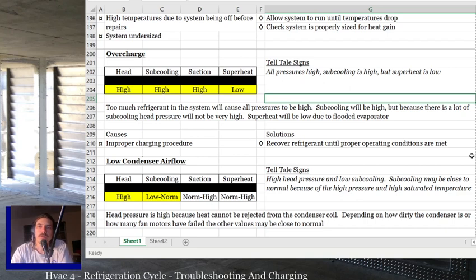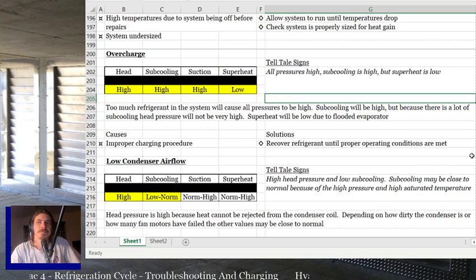Usually you can spot an overcharge instead of other issues because even though all this stuff is high, because you have the high subcooling, the head pressure isn't that high. I don't know how else to explain it. It's going to be slightly higher than normal. I mean, if they really overcharge it like 4 or 5 pounds, you might start getting close to where you're about to trip the pressure switch. But usually the overcharge doesn't do that because your subcooling ends up getting higher and higher and higher, and that kind of drives the head pressure down a little bit.